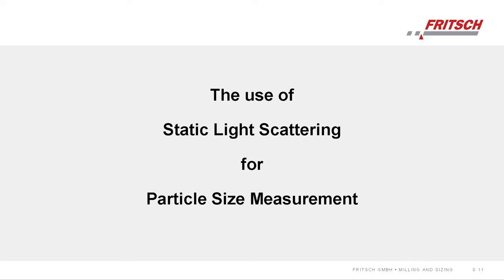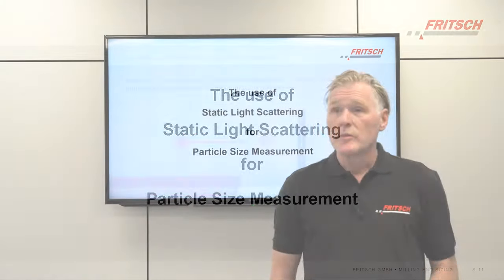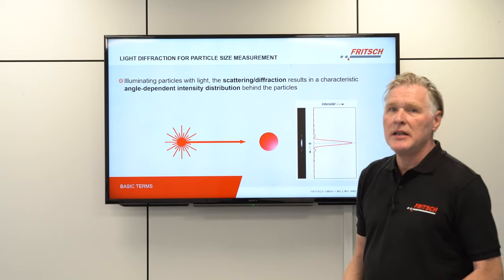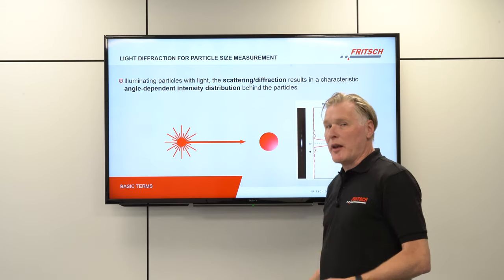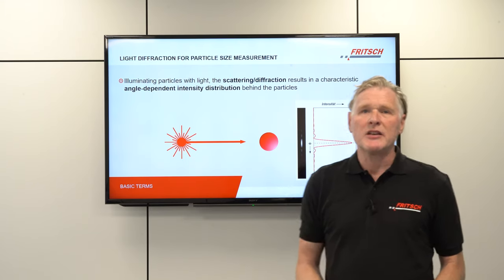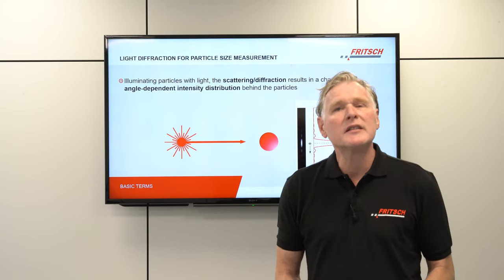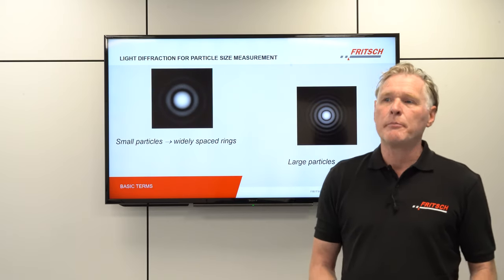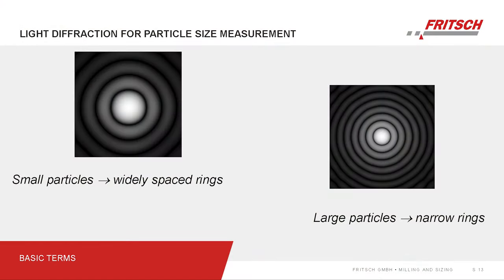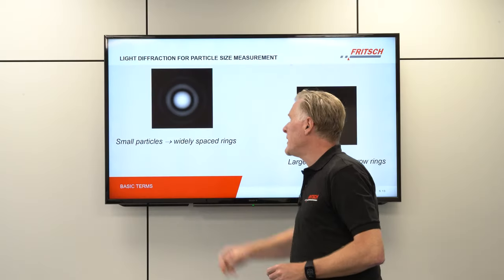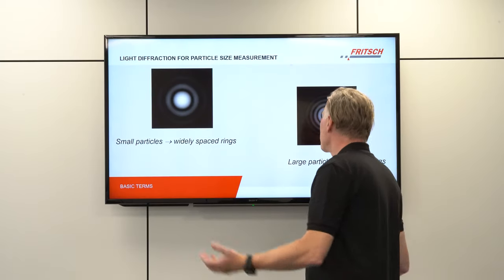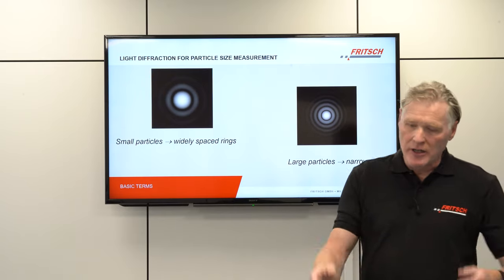Now let's talk about the theory behind laser diffraction, also called static light scattering. We illuminate a particle typically with a laser light and observe an intensity distribution, from which we then calculate the particle size. Typically small particles generate large scattering angles while large particles create small scattering angles. This means small particles give wide diffraction rings while large particles give narrow diffraction rings.